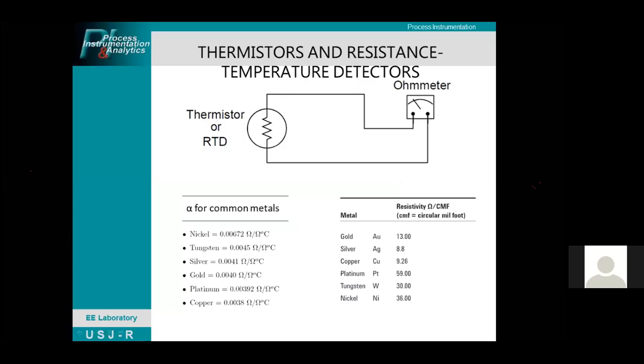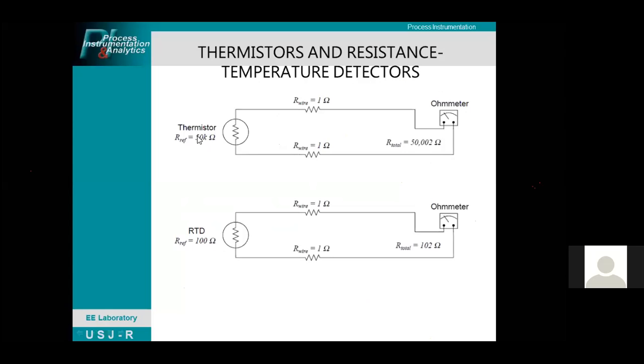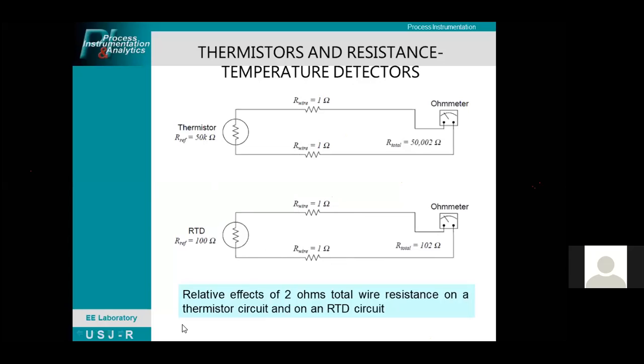Okay, so consider a thermistor with a reference resistance of 50k ohms, with lead lines equal to 1 ohm each. The resistance of the conductor is given as 1 ohm each, then the reading of the ohmmeter will be 50,002 ohms. Compared to the RTD with a reference resistance of 100 ohms, having the same conductor resistance of 1 ohm for each line, the reading is 102 ohms. Okay, so you can see the difference between the thermistors and the RTD. So the relative effect of 2 ohms total wire resistance on the thermistor circuit and on the RTD circuit.